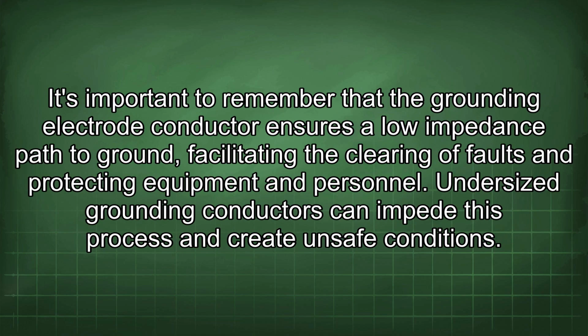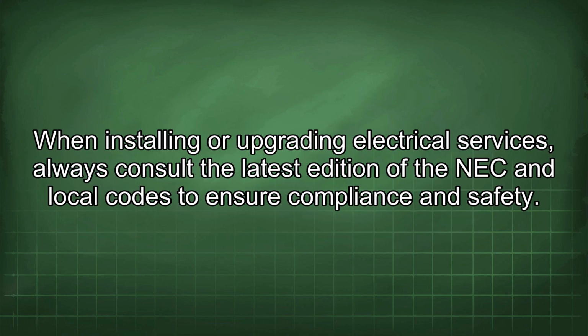It's important to remember that the grounding electrode conductor ensures a low impedance path to ground, facilitating the clearing of faults and protecting equipment and personnel. Undersized grounding conductors can impede this process and create unsafe conditions. When installing or upgrading electrical services, always consult the latest edition of the NEC and local codes to ensure compliance and safety.